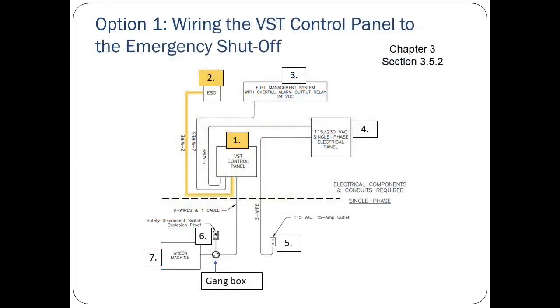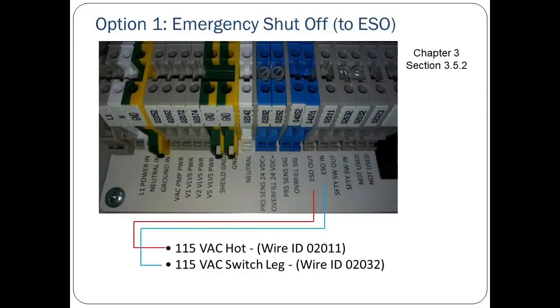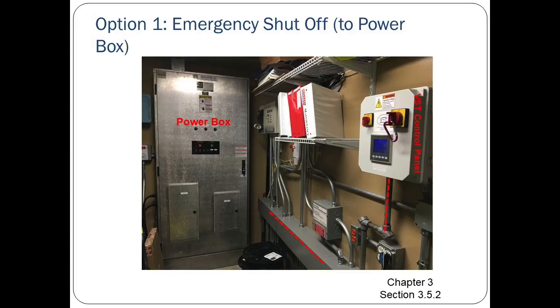Next, for Option 1, we're going to discuss the 2 wires that must be run between the VST control panel and the emergency shutoff, or ESO. The ESO circuit is located inside the hut, inside the power box. The ESO circuit is usually a part of a shunt circuit and must be wired as such. Here's where the wires that run between the VST control panel and the emergency shutoff system are to be terminated. The emergency shutoff relay that is on the other end of the wires is located in the power box inside the GDF or data hut.